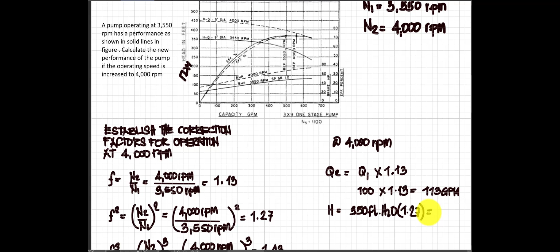Then, for the head naman, if we have yung head, so that will be the value of your head. So, for example, dito, we have your head, which is equivalent to 350, no? Yung RPM do, 3,550. Head niya is 350 feet. So, I'm going to multiply it, 350 feet of H2O, multiplied by 1.27. So, for head. Okay. So, we have the value of 444.5. So, this is feet of H2O.